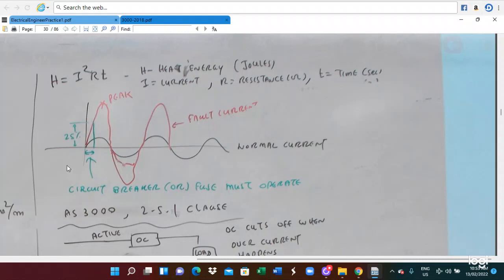So the fault current, normal, this is the blue one is the normal current, and the red one is the fault current. So when the fault current happens, the fault current is much more than the normal current. So the circuit breaker needs to operate before the fault current level reaches the maximum. When it reaches 25% of the peak, the circuit breaker must operate. Otherwise, once the fault current reaches the maximum point, the equipment has already been damaged. So there is no point in providing the protection equipment.